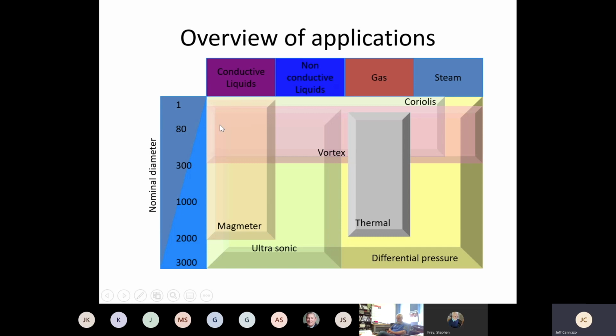Ultrasonic meters today actually move into the gas area as well, but they can measure both conductive and non-conductive liquids. And they really go to the full line size because we have clamp-on technology. We can go outside the pipe or even drill through the pipe with a hot tap and insert the sensors right inside the pipe. So ultrasonic meters are a good solution. They tend to be for clean liquids. We call them clean, but they can actually have up to 5% solids. So sludges will work with transit time ultrasonic meters.